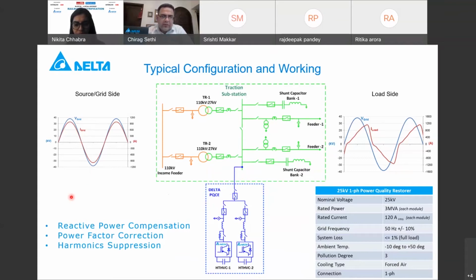Our solution is addressing the triple problems of reactive power compensation, power factor improvement, as well as harmonic suppression. This is a modular kind of product where, depending on the reactive power requirement, you can add on multiple units. In the case of a typical TSS of, let's say, 20 MVA contracted maximum demand, what we provided here in the case of Southern Railway was a 6 MVA configuration. In the case of a metro, where the traction loads are maybe not more than 10 MVA, it was a 3 MVA product which we installed.